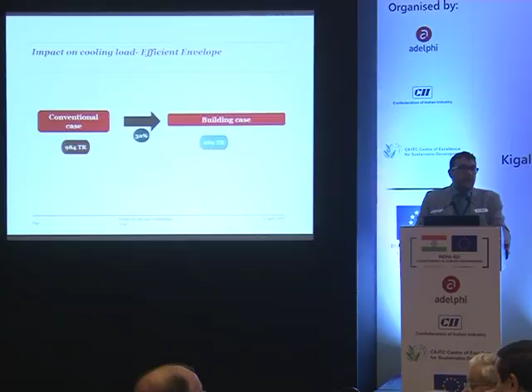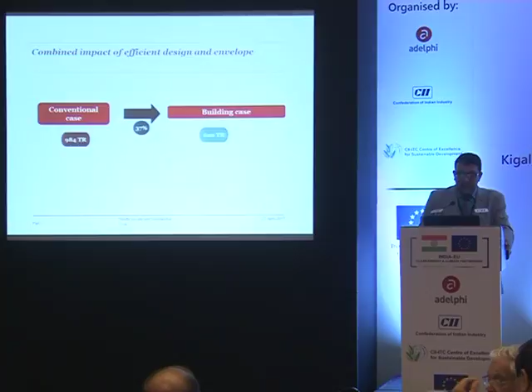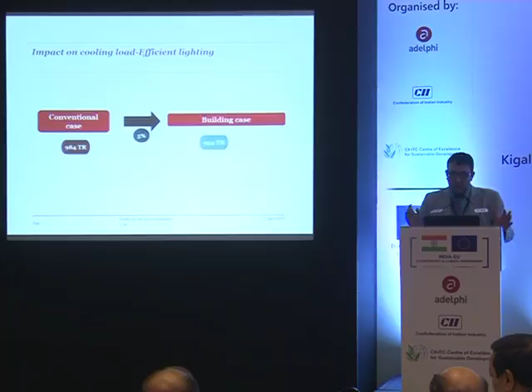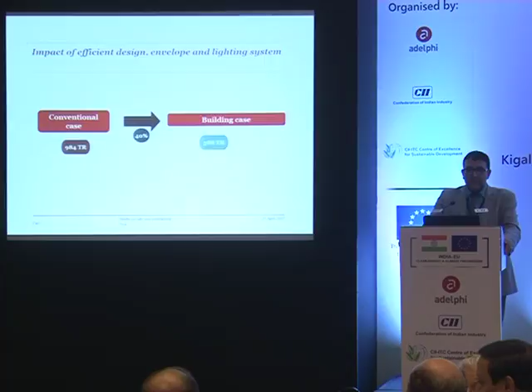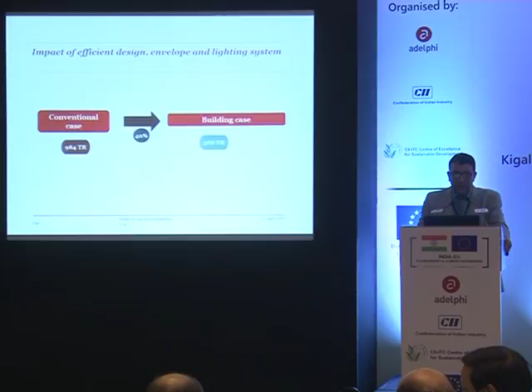So what is the impact on cooling load through an efficient envelope? We see a reduction close to 25 to 30% in cooling load requirement. Lighting has an impact of close to 5%. So if we combine efficient design, envelope, and lighting system, we get a 30 to 40% drop in cooling load requirements. This is all indicative of what I've discussed.